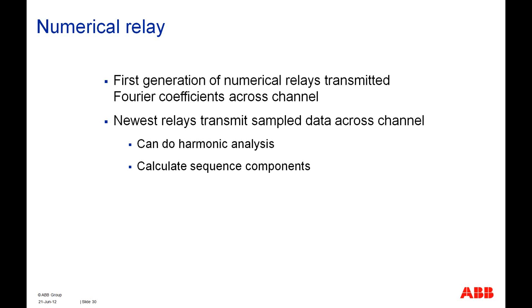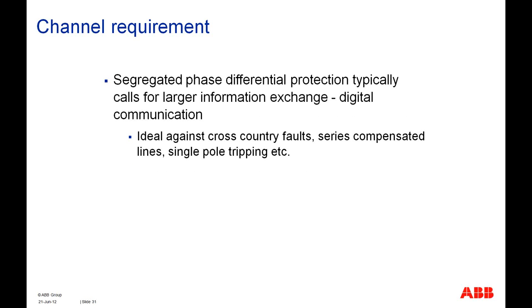With the advent of the numerical relays, now we can calculate the harmonic analysis, as well as the sequence components, and that really gives us an added advantage in calculating the line differential protection quantities. In segregated phase differential protection, we have to communicate a large amount of digital data to be exchanged. Therefore, the channel requirements are also quite stringent for line differential protection, and we will have a discussion about those requirements later on in this presentation.